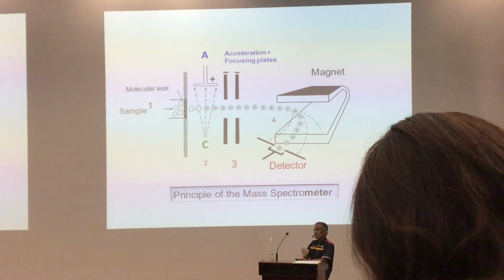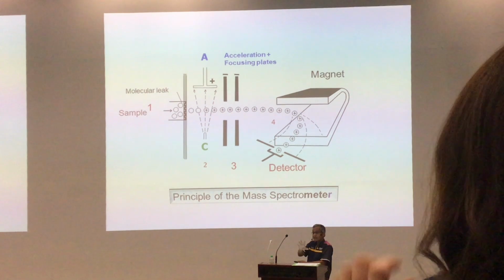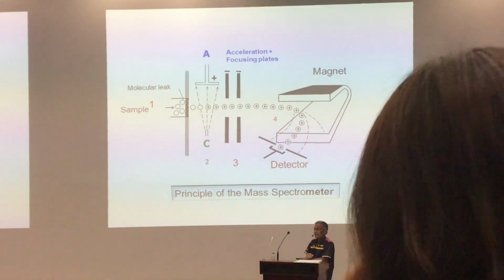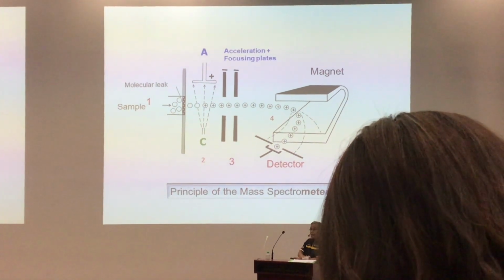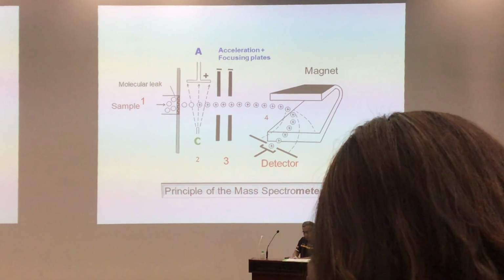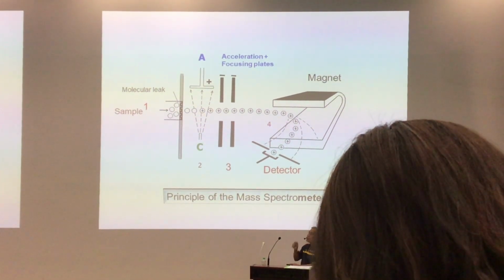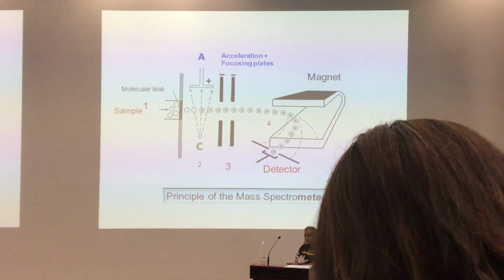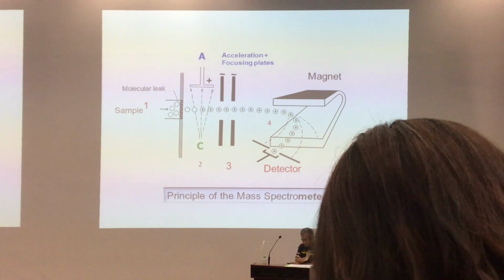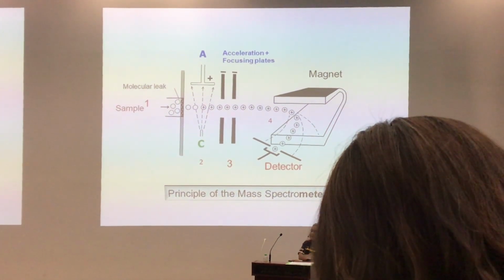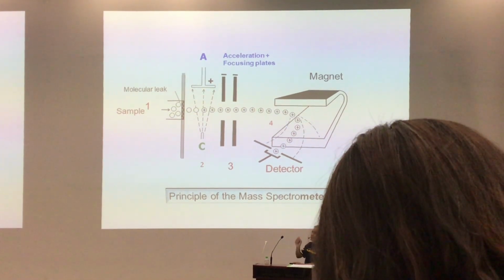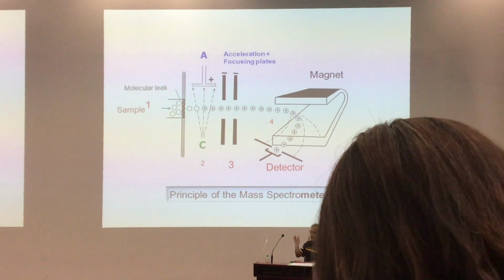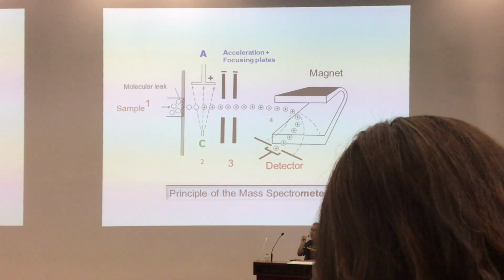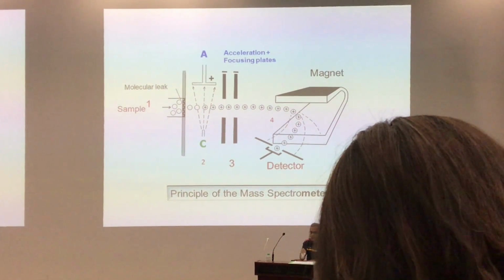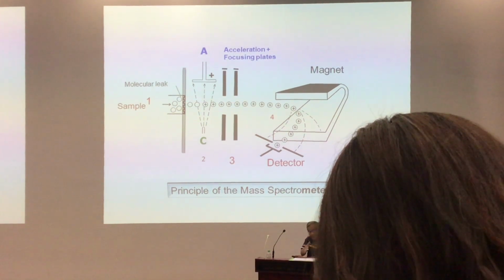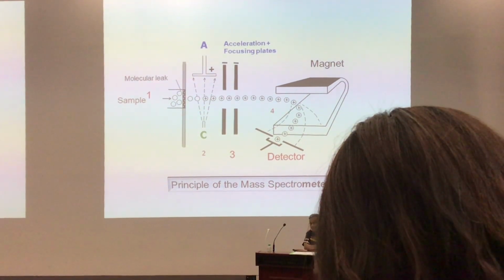This is the mass spectrometer, based on the molecular weight of the gas. The heavier the gas, the least deflection after the magnet. The lighter the gas, the most deflected. For example, oxygen has molecular weight 32, CO2 44. So oxygen will be more deflected compared to nitrous oxide or CO2, right? As simple as that. Then they calibrate. The setting for oxygen is 32, CO2 44. Then they calibrate accordingly. So if the molecule of the gas falls at this spot, it belongs to CO2 because molecular weight 44, oxygen 32. Then they get say 10 measurements, 20 measurements at the same setting, same time.